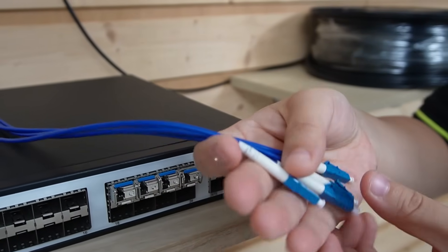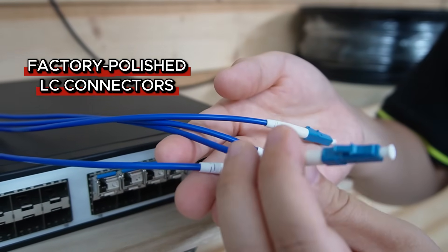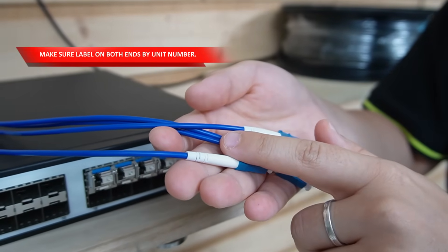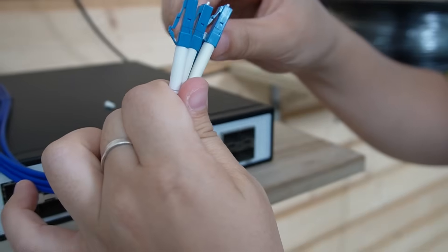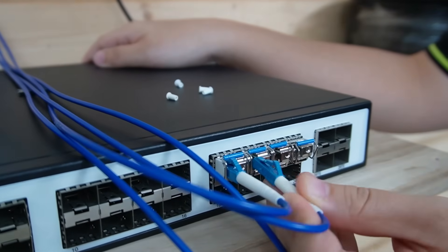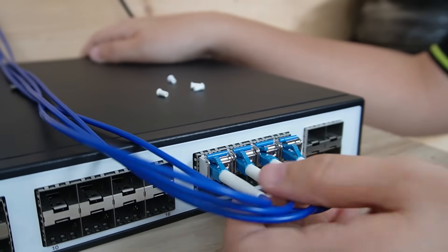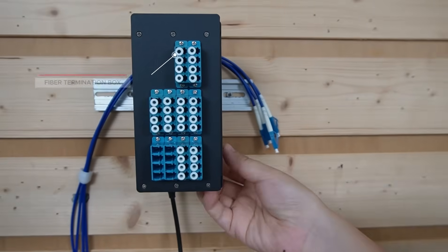For our project we're using pre-made single-mode fiber — it's the plug-and-play option. Factory-polished LC connectors on both ends, and you can measure to length. It's fast, clean, and perfect if your pathways are friendly. Make sure you label both ends by unit number — your future self will thank you. Let's take out the dust caps. I'm going to plug in all four of them. The fiber patch cord is going to go all the way to our termination box here.